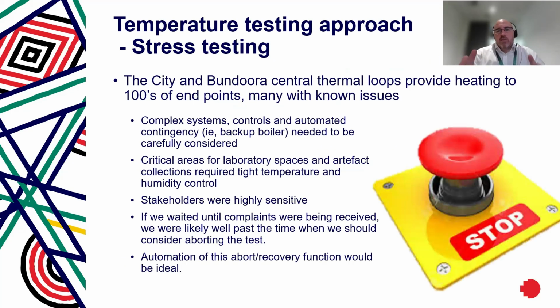So temperature testing, the approach, we called it stress testing of the portfolio to see what our real world capacity was. It's very difficult to define that based on a desktop analysis because there's so much diversity and literally thousands of FCUs that we need to consider. So it was a complex system. We needed automated contingency. So we had to consider that in the design of the testing. If anything was going wrong in the testing, by the time we found out that something was going wrong, there would be an inability to recover within a reasonable time frame.